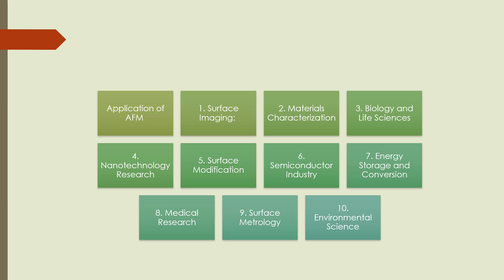Looking at the applications of atomic force microscopy, it is used in surface imaging, surface modification, and surface metrology. AFM is widely used for imaging surface topography at the nanometer scale, providing detailed information about surface features, morphology, and roughness. It is also used in material characterization, enabling characterization of properties such as stiffness, elasticity, adhesion, and friction at the nanoscale.